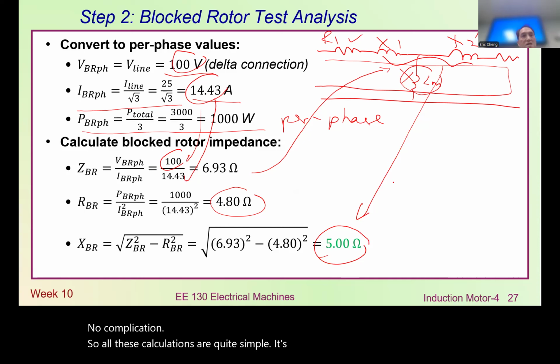But anyway, we also need to understand the temperature coefficient. Now we are calculating the equivalent coefficients. All the coefficients R1, X1, R2, X2 are mostly the series components, the lumped components that can be calculated or measured by the block rotor test. Bear in mind, because we are now using the operation temperature of 75 degrees C, the R1 resistance we calculate is only for 25 degrees, so we need to calculate it at 75 degrees. Otherwise, the calculation is not sensible.